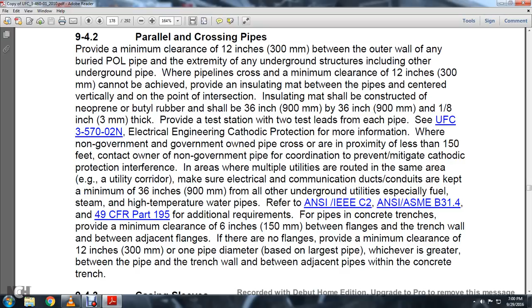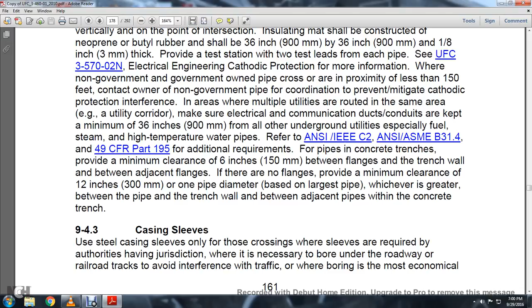9.4.3 Casing sleeve. Use steel casing sleeves only where crossings require sleeves by authorities having jurisdiction, or where it is necessary to bore under a roadway or railroad tracks to avoid interference with traffic. Where boring is the most economical construction method, consider planning construction and operation of trench crossings, considering economics, installing spare casing sleeves and eliminating excavation for future fuel lines. Ensure the design provides isolation for the fuel carrying pipes at the contact with the casing pipes.